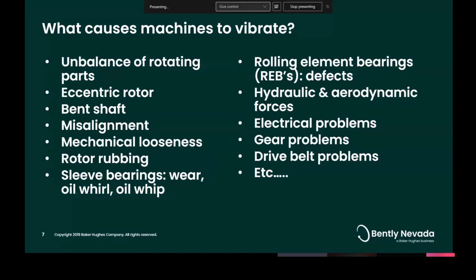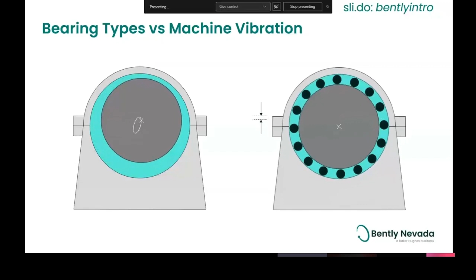How a machine vibrates also depends on the type of machine that it is and the type of bearings that are on that machine. On the left, we have an example of a sleeve bearing or an oil film bearing. And on the right, we have an example of a rolling element bearing. If you were to trace the path of the center line of those shafts, the path would actually be the same. But because the left bearing has an oil film to move within, the machine overall reacts very differently than the one on the right, which is constrained by those rolling elements and is thereby forcing the entire machine to move. So these are also considerations of what the vibration is going to look like, and will also lead to how you choose what sensors to use on those machines.